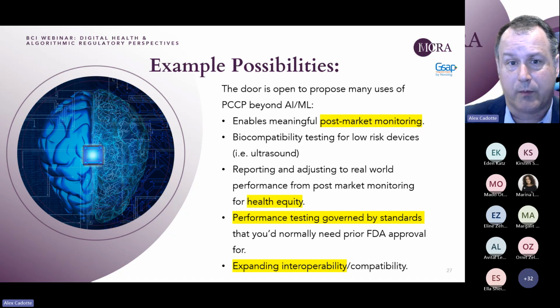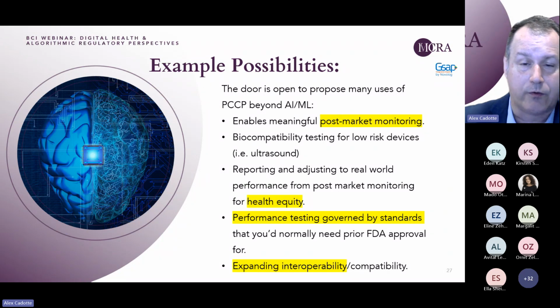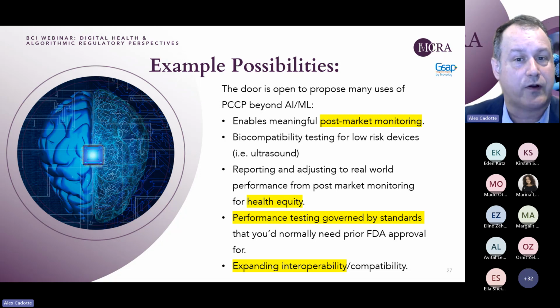Some other ideas for PCCP might be things like biocompatibility testing for low risk devices. One example would be ultrasound, where often minor changes in the composition of a probe could be accommodated with a PCCP, as long as you have the right procedures and processes available to come to those conclusions and set reasonable thresholds for that biocompatibility testing passing.